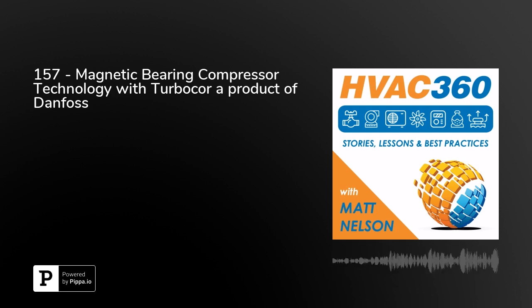As far as the percentages go, what sort of energy savings can you get going from an oil-based compressor to a magnetic bearing? The area where you'll see significant benefits in performance is part load operation. If we benchmark our compressor against a baseline traditional fixed speed screw compressor, you can see efficiency improvements as high as 30 to 40%. All of our compressors are oil-free and also come standard with variable speed drives, so they can adjust power consumption, especially at low load conditions when capacity is not required.